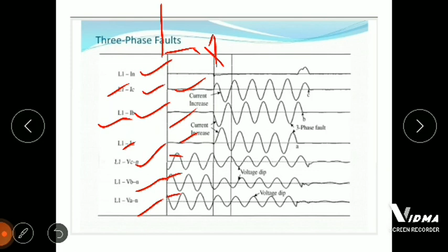Suddenly, if there is a disturbance in the overhead transmission line, we can say that there is a three phase fault. A three phase fault is a short circuit of all three phases, with the ground terminal. At the point of this fault, our current will increase, and it keeps increasing unless we clear the fault. You can see that the current increases in the C phase, similarly in the B phase, and similarly in the A phase. And as the current increases, the voltage dips.